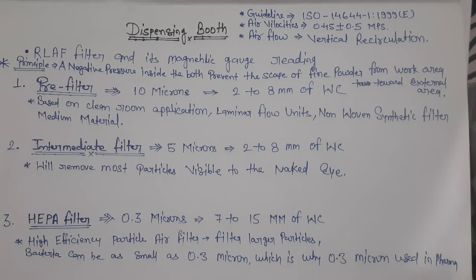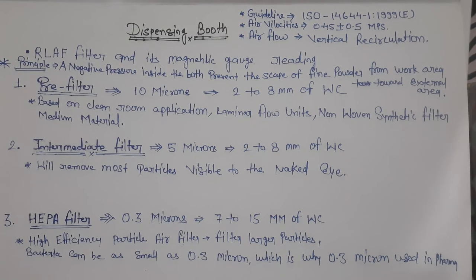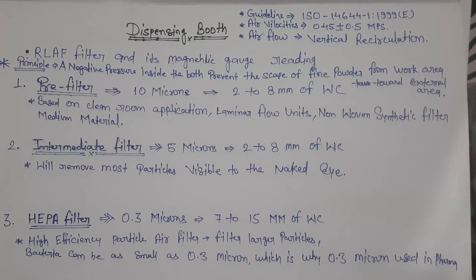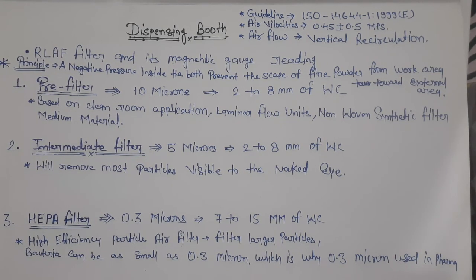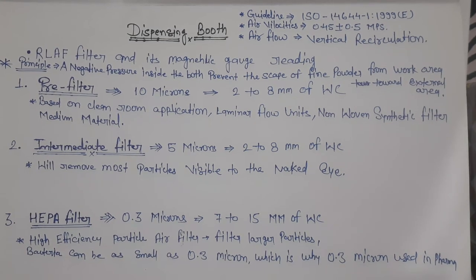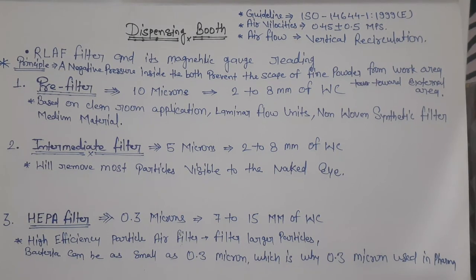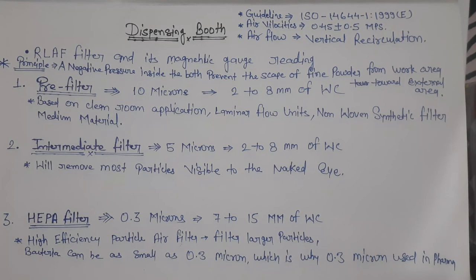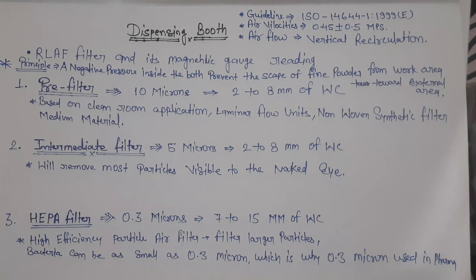The third one is HEPA filter. HEPA filter size is 0.3 microns and manometric gauge reading is 7-15 mm of water column. The full form of HEPA filter is High Efficiency Particulate Air filter. It filters larger particles — bacteria can be as small as 0.3 microns, which is why 0.3 microns is used in pharmaceutical industries in dispensing booths and other areas. Thank you, everyone.